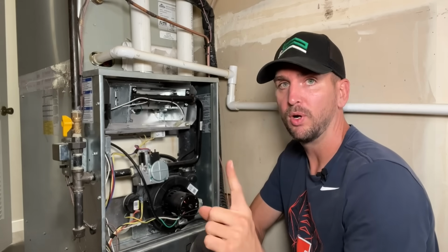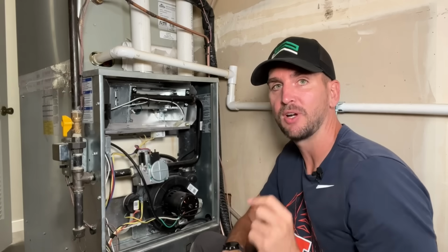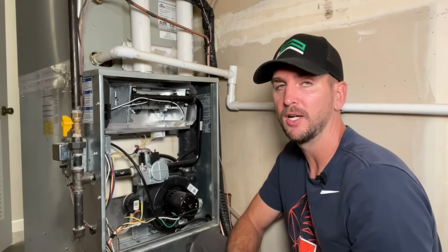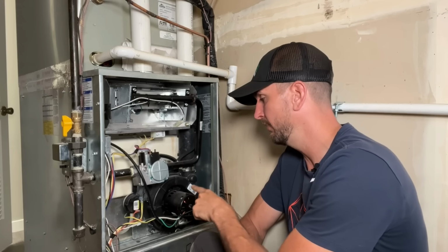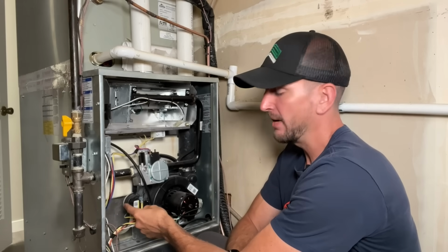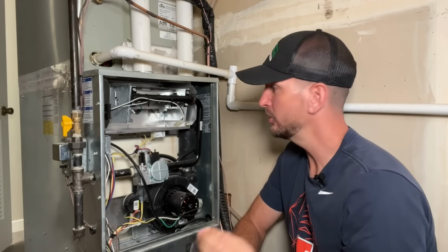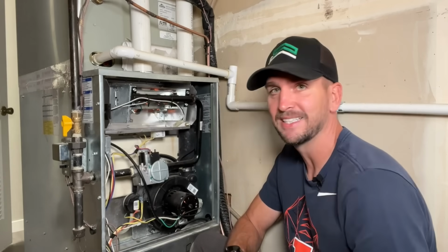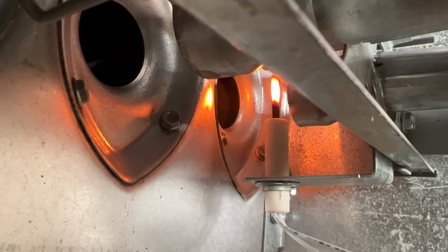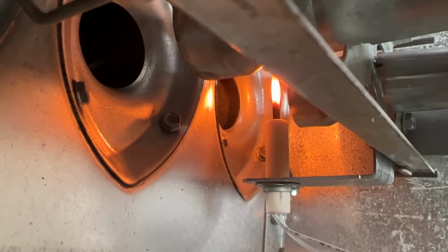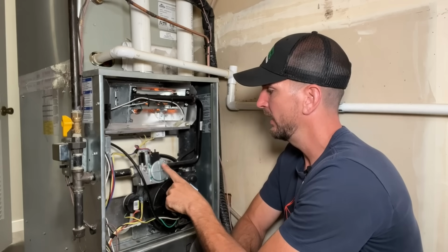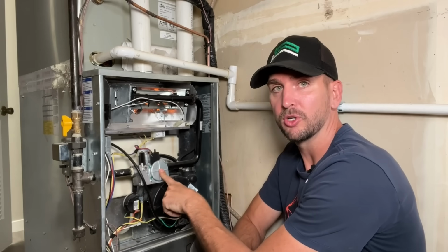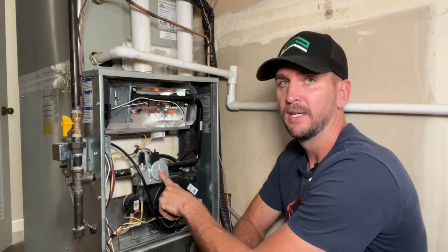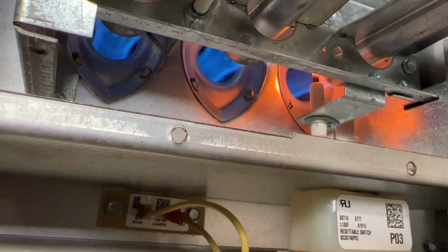So step 1 in this process is going to be your draft inducer motor turning on. So here a motor startup, then the draft is confirmed by a pressure switch. Once that's confirmed, you'll see an igniter glowing hot. That's step 3. Once that glows hot for a few seconds, you'll have a relay in step 4 where your gas valve turns on and then the burners will light.